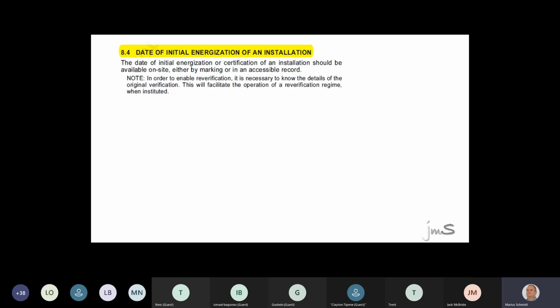Now, if you go to a house and it's only fuses, then you know it's prior to 2003. After 2003, RCDs came in. You see that I can start looking at certain things. If I look in the ceiling and I see this plastic cable, it looks like material around it. Have you seen them? Well, that also tells me it's the 70s, maybe early 80s. If I look at TPS and I look at the phase neutral earth, there are times that the earth is only copper, there's no plastic around. That is also 70s and early 80s. So guys, that is how you broaden your knowledge and start knowing what's in and when out and whenever to do it. Any questions?